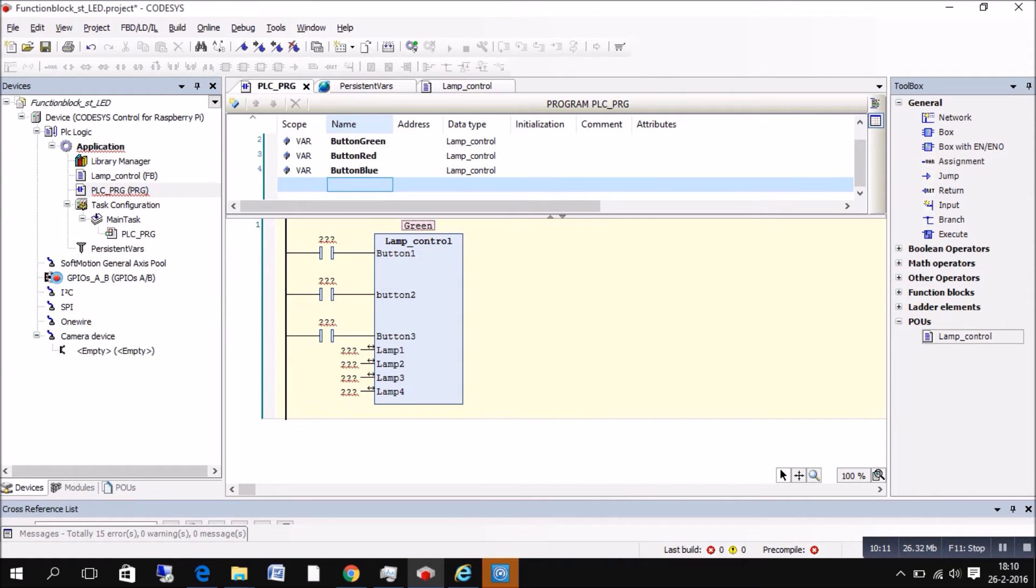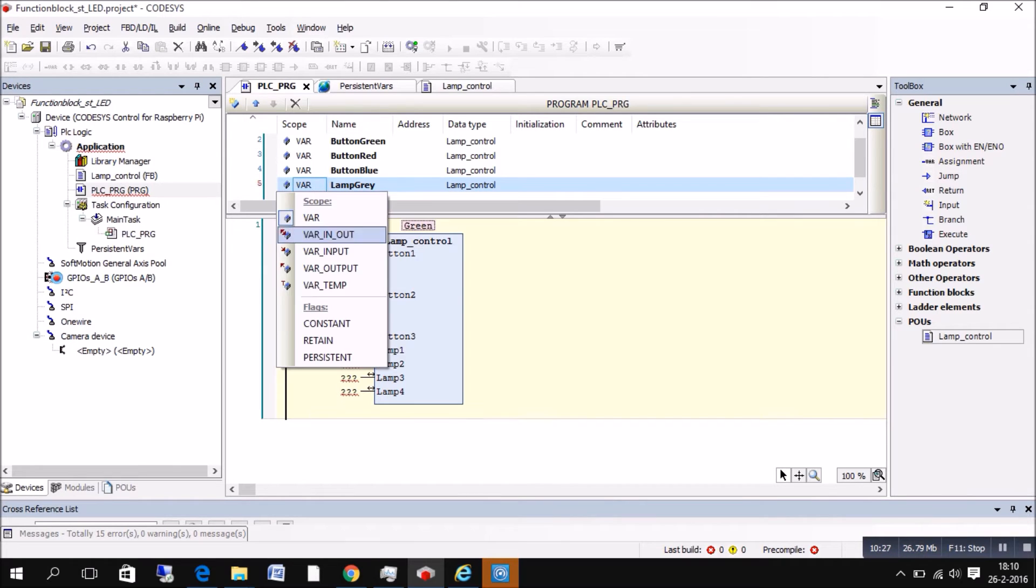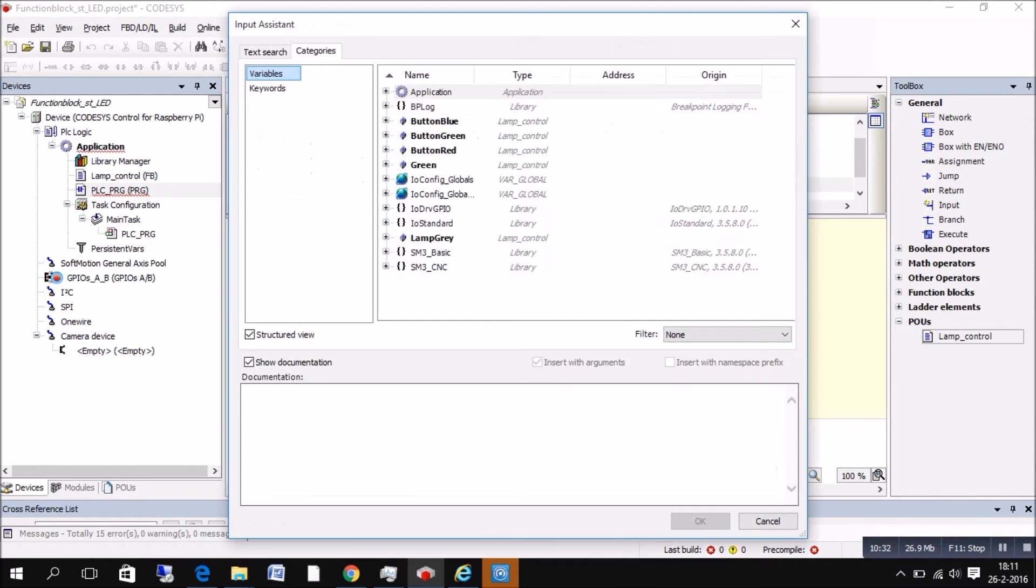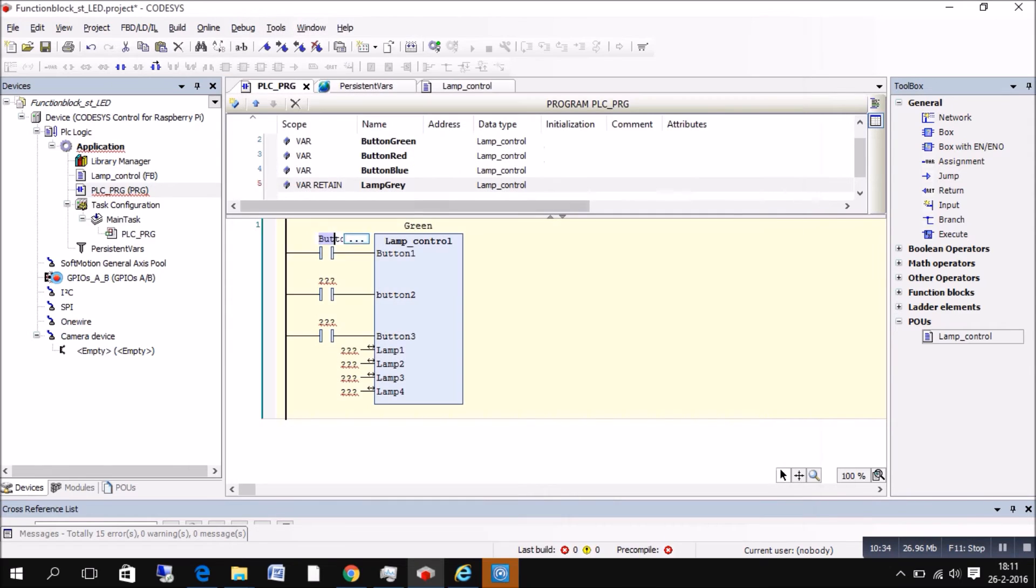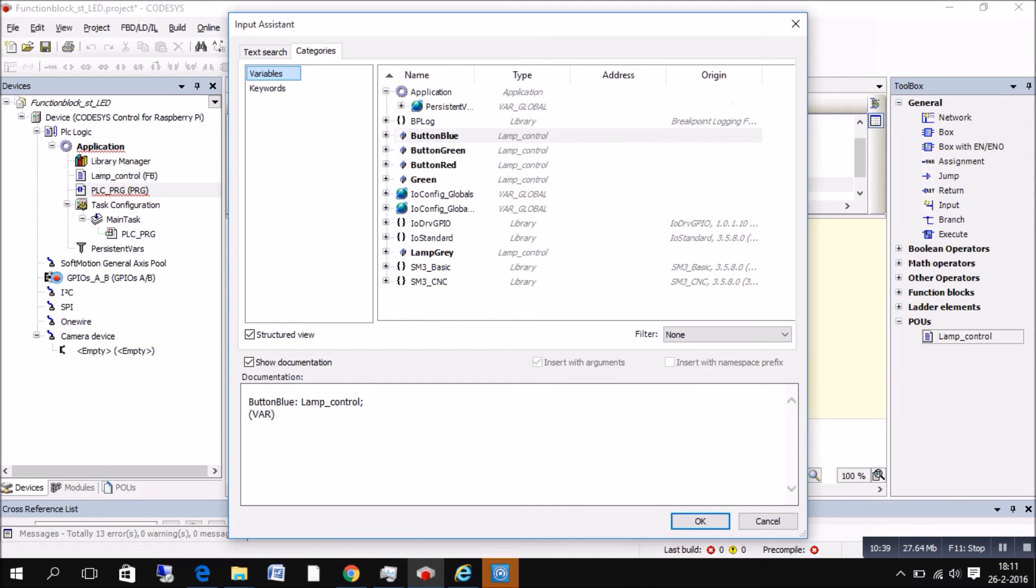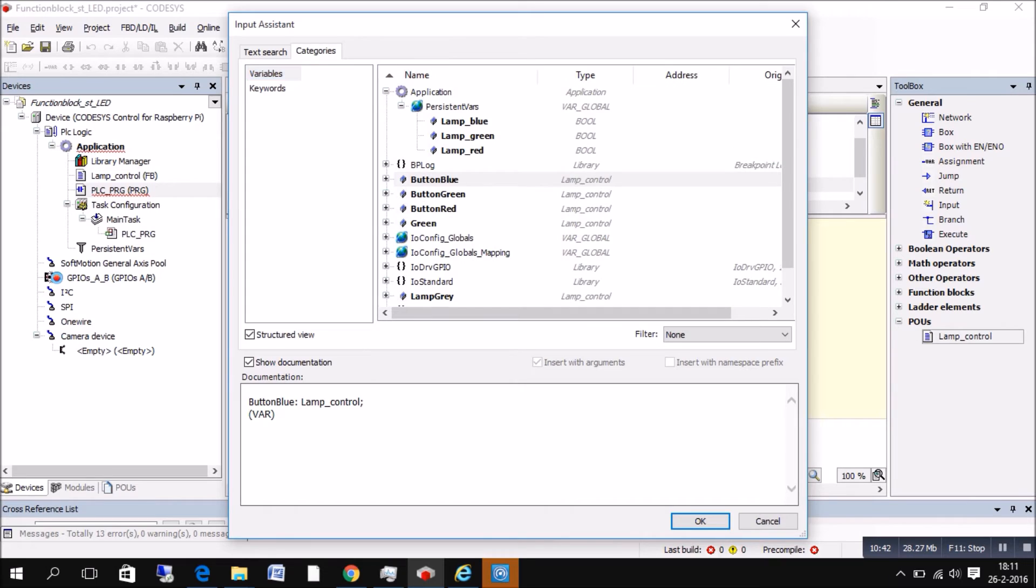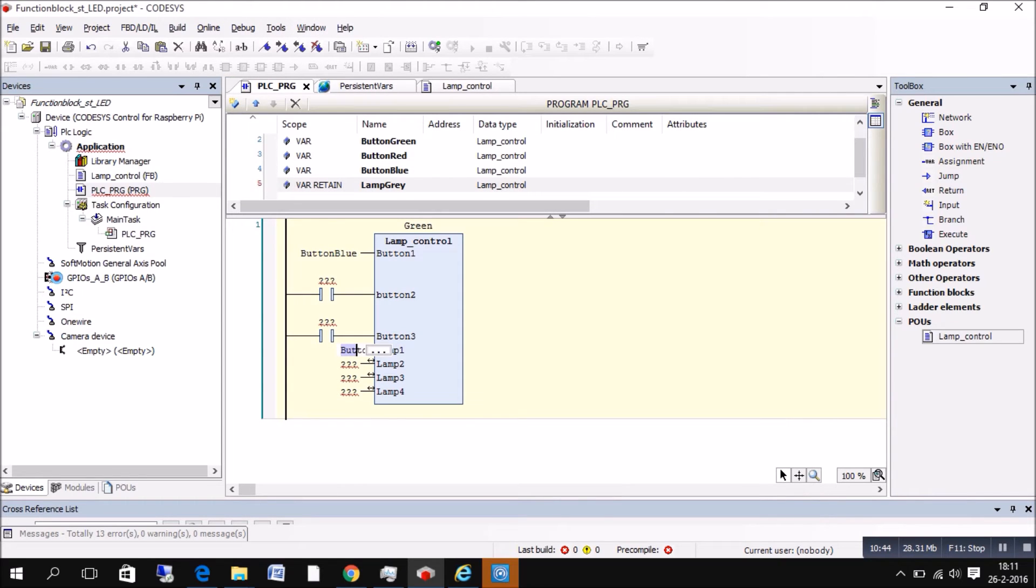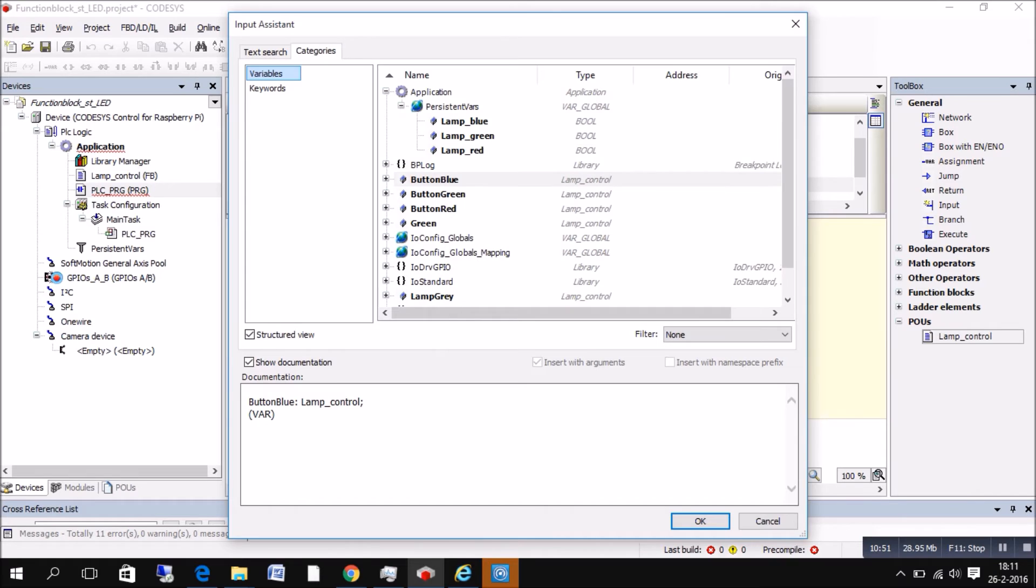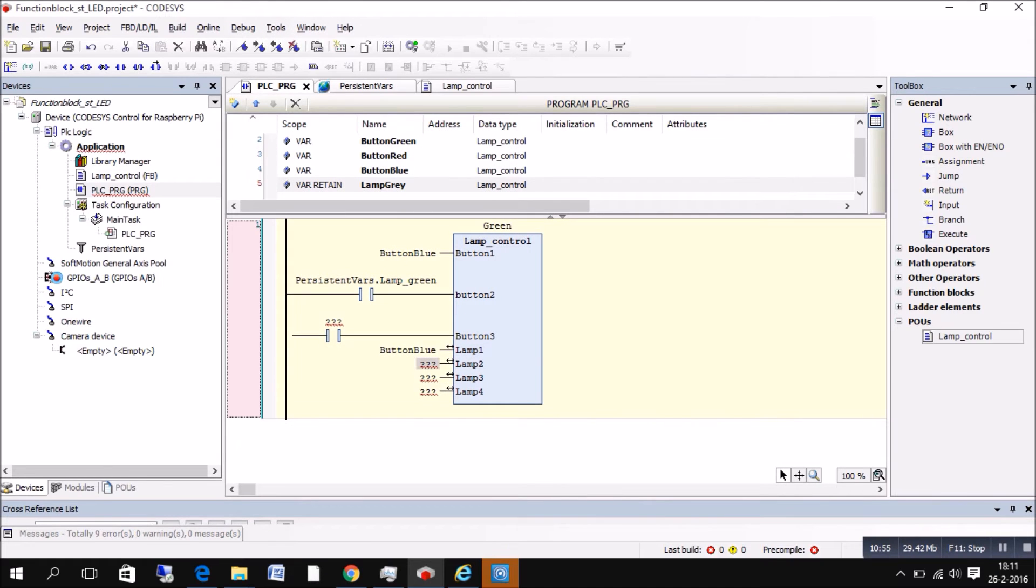We're gonna set the var at the very end. We're gonna set it to var and then the option beneath it, retains. So it will write the variable to the memory if it changes. With all the benefits if it reboots, it will take the last position it put it in. So now we're gonna select all the variables, put them at their place. So always select them and the bar next to it with three dots. Always pick the variables from that.